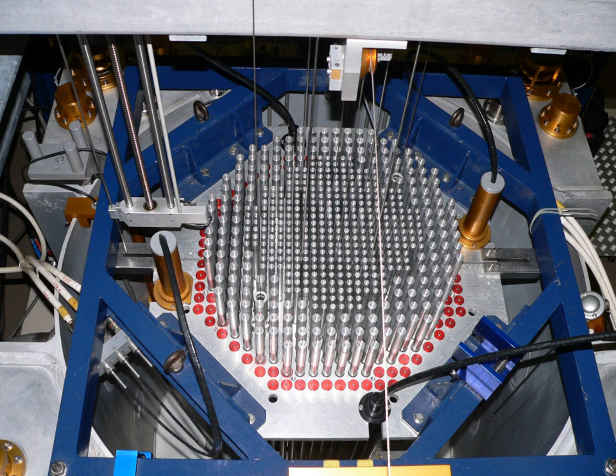Boiling water reactor BWRs are characterized by boiling water around the fuel rods in the lower portion of a primary reactor pressure vessel. A boiling water reactor uses U-235, enriched as uranium dioxide, as its fuel. The fuel is assembled into rods housed in a steel vessel that is submerged in water. The nuclear fission causes the water to boil, generating steam. This steam flows through pipes into turbines. The turbines are driven by the steam, and this process generates electricity. During normal operation, pressure is controlled by the amount of steam flowing from the reactor pressure vessel to the turbine.